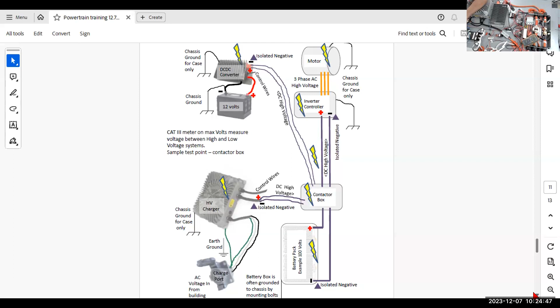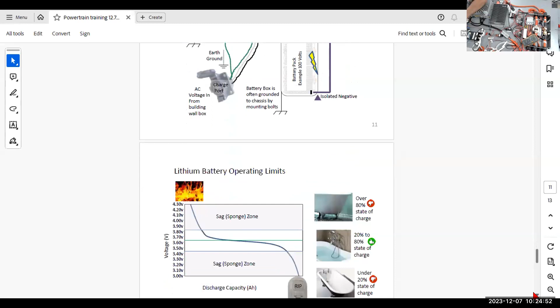There is, by the way - you're not going to remember the number - but there is a specification: you're allowed 500 ohms. There are actually 2 different specs for it, but you're allowed 500 ohms per volt of resistance between your high and low voltage systems. That's how the computer figures out whether or not it's within the right tolerance.